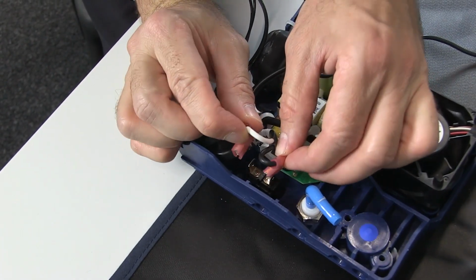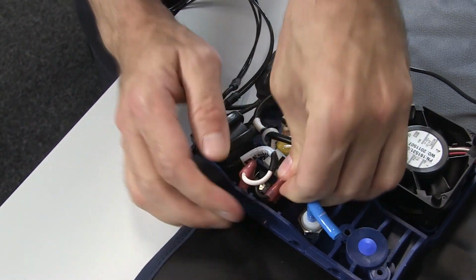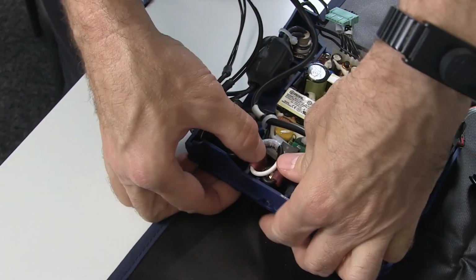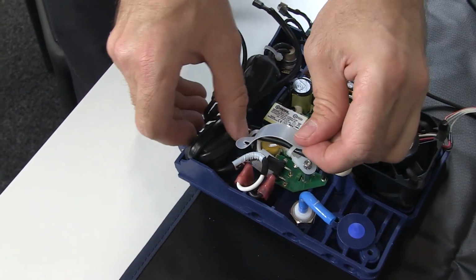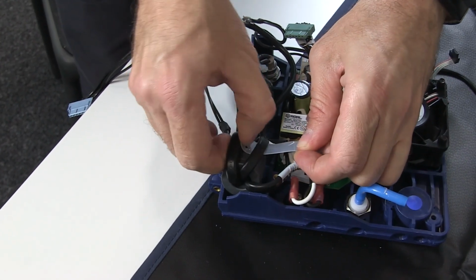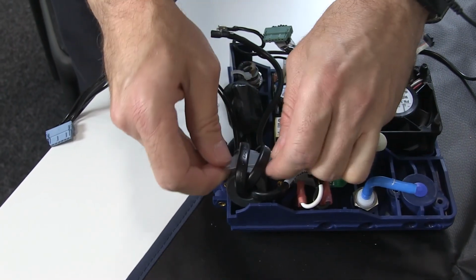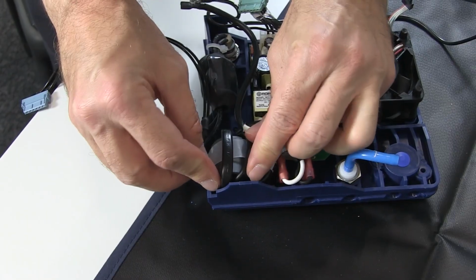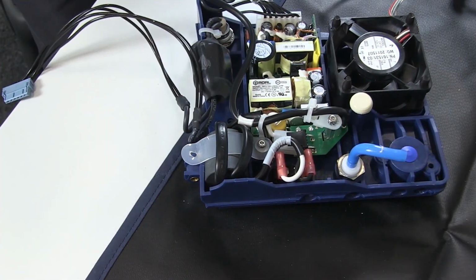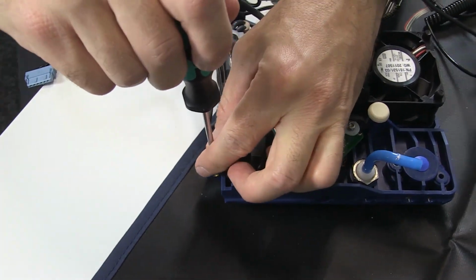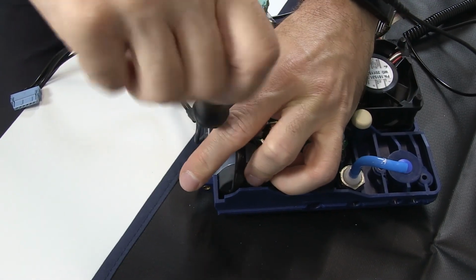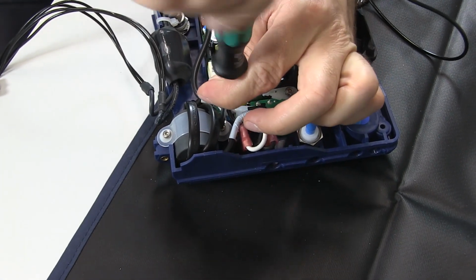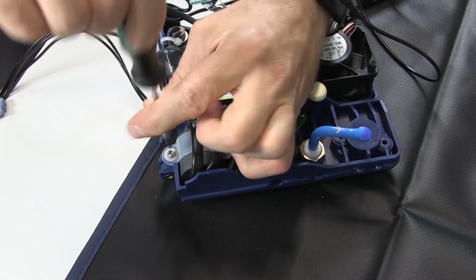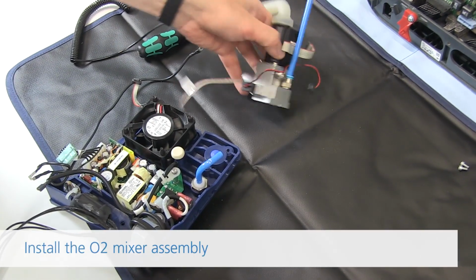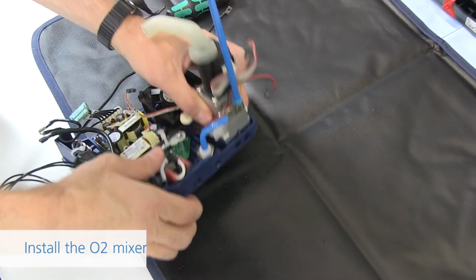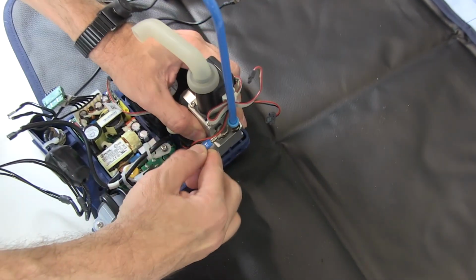Connect the 2 terminal cables from the AC power input cable to the 2 terminal lugs of the AC power plug on the connector plate. Put the ferrite in position, then install the clip on the ferrite. Tighten the 2 screws to keep the ferrite and the clip in position. Position the mixer assembly on the connector plate. Attach the blue low pressure oxygen tube and install the 2 screws.